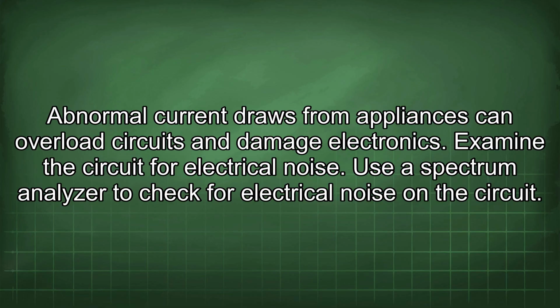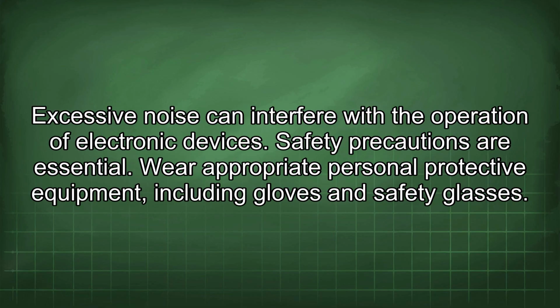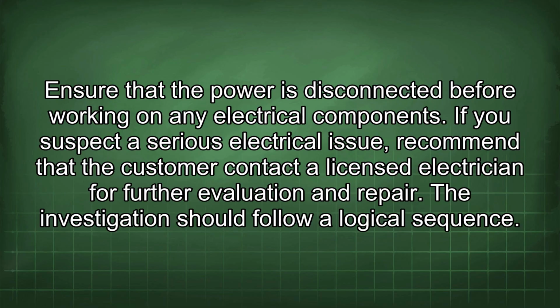Examine the circuit for electrical noise. Use a spectrum analyzer to check for electrical noise in the circuit. Excessive noise can interfere with the operation of electronic devices. Safety precautions are essential. Wear appropriate personal protective equipment, including gloves and safety glasses. Ensure that the power is disconnected before working on any electrical components. If you suspect a serious electrical issue, recommend that the customer contact a licensed electrician for further evaluation and repair.